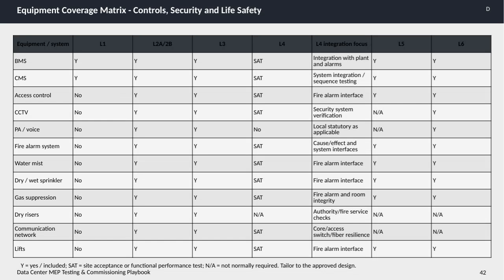On this slide, we have the equipment coverage matrix, which focuses on controls, security, and life safety systems within the data center MEP testing and commissioning playbook. The matrix breaks down various equipment and systems across different testing levels, from L1 through L6. You'll notice that essential systems like the building management system, central management system, access control, CCTV, and fire alarm system are consistently included from L2A/2B upwards, with site acceptance testing emphasized at L4. This level typically involves thorough functional performance testing to ensure systems operate as designed in the actual environment.